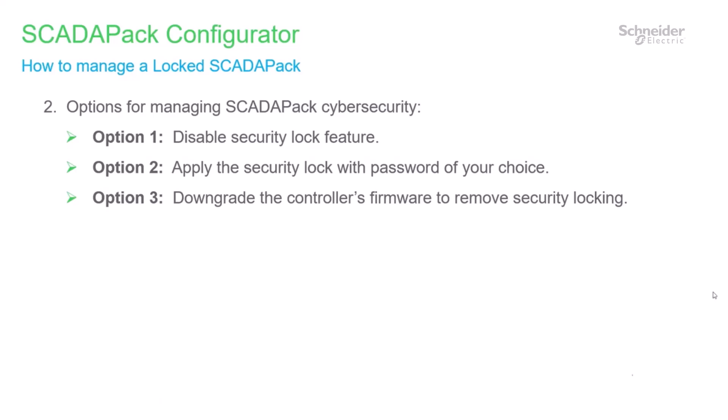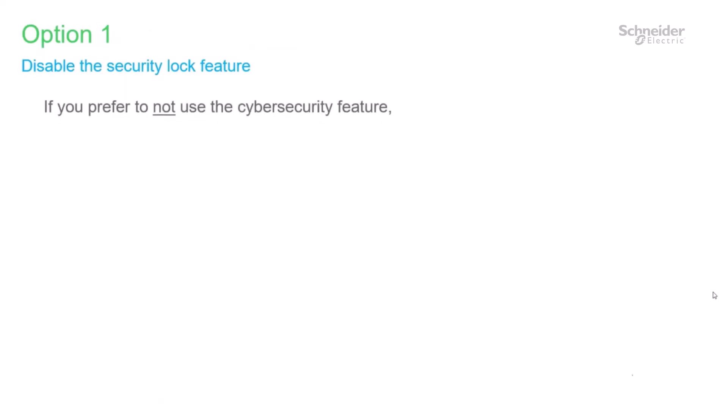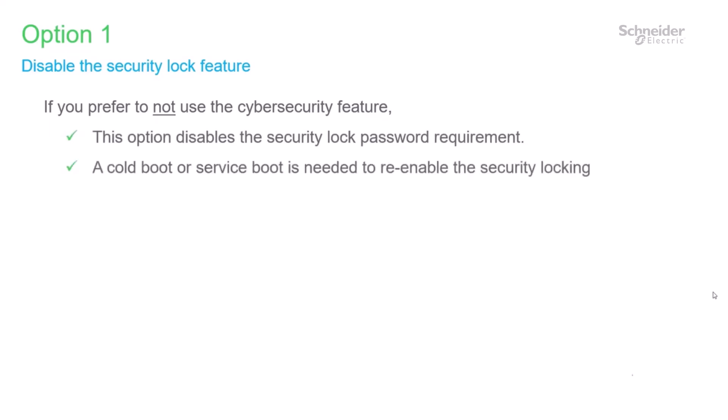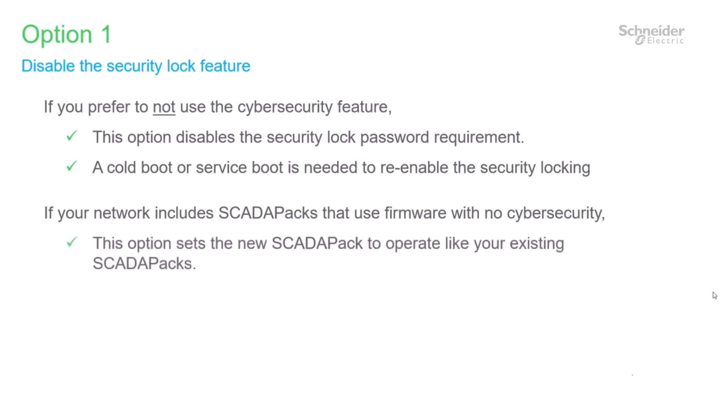We will discuss option 3 later. We begin with option 1, how to disable the security lock. Note that the device must be unlocked or lock feature disabled in order to edit and write configuration changes to it. This option will disable the requirement for a security lock password. A cold boot or service boot is needed to re-enable the security locking. If you have other SCADA-PACs on your network that use firmware without cybersecurity feature, this option will set the new SCADA-PAC to operate like the existing SCADA-PACs. I'll select SCADA-PAC Configurator to demonstrate now.